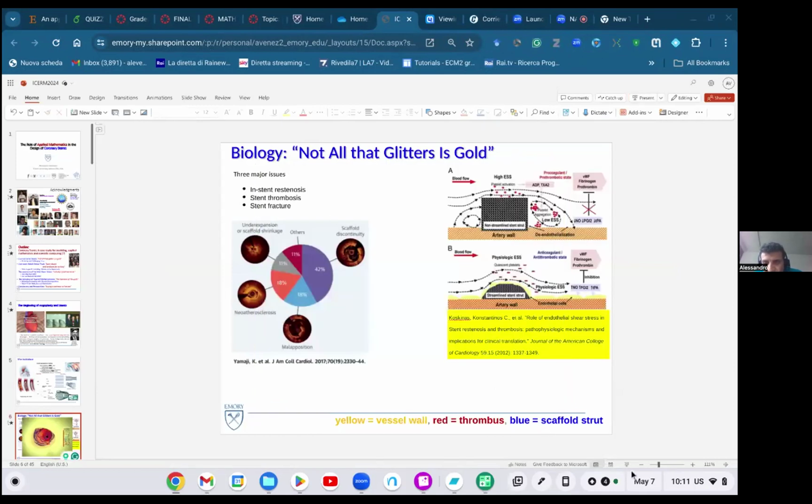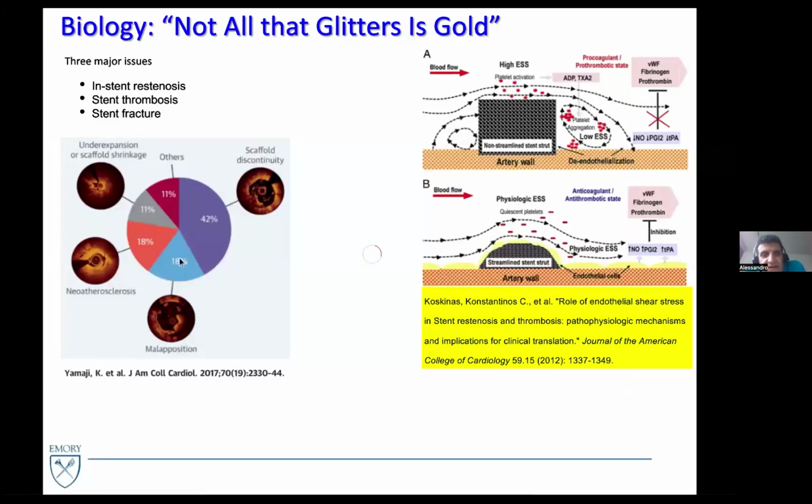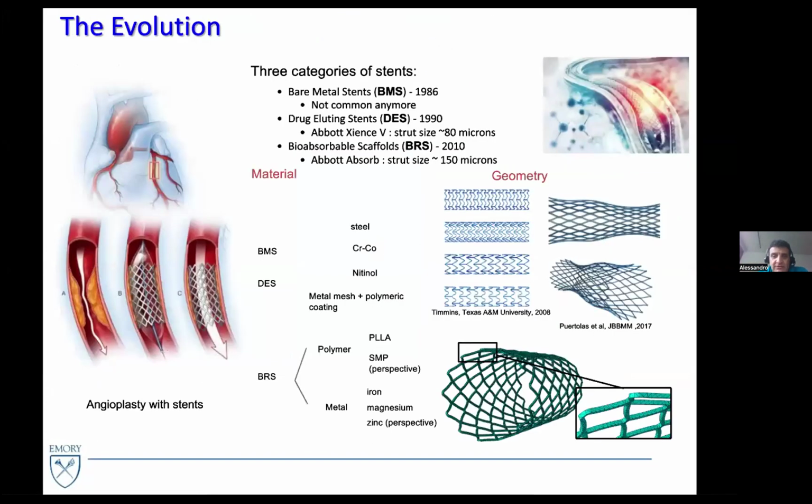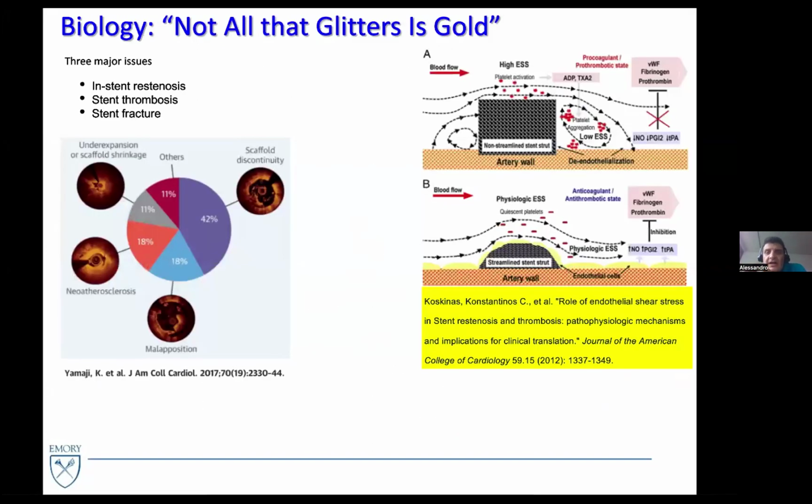The point is that in order for the strut with the non-metallic material to stand the pressure of the balloon, which could be around 15 atmospheres, these struts must be thicker than regular struts for drug-eluting stents.